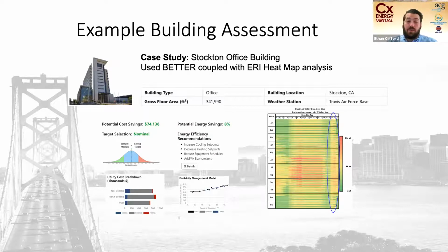After digging in more, I was able to see that they have an ice storage or some kind of thermal storage system on site. Comparing the two together, I figured out they have a change point model that's kind of flat, and the ice storage system is causing the issue. These cooling and heating set points are probably a result of that. Then the economizer problem was something to note, to see if that was a reason for the part load efficiency losses.